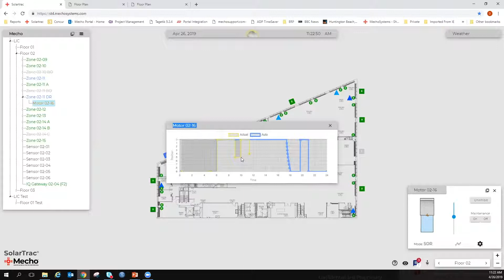It tells me that at 9 o'clock there was a brightness condition. It moved to position 4 and stayed there until 10 o'clock when the brightness condition wasn't prevalent anymore, then it moved all the way up. I've just moved the shade down to position 4 as a shade override.